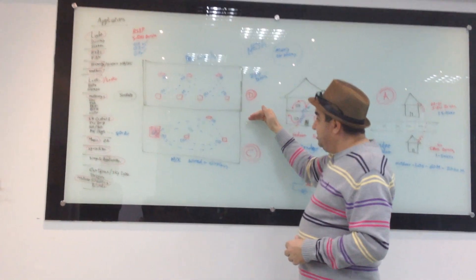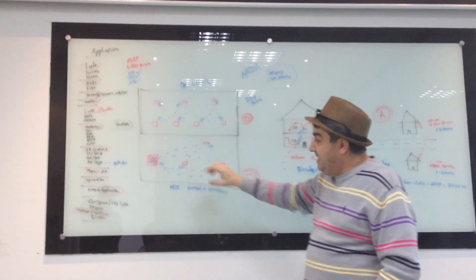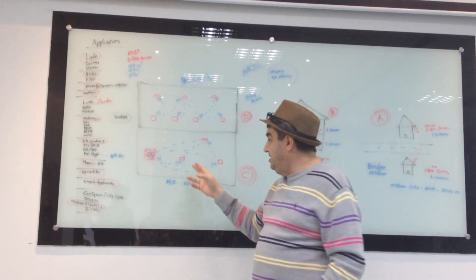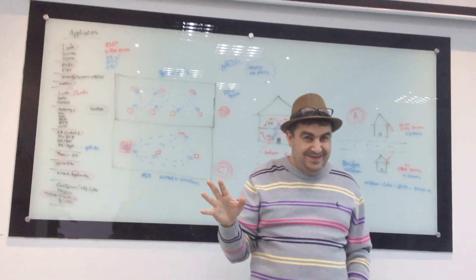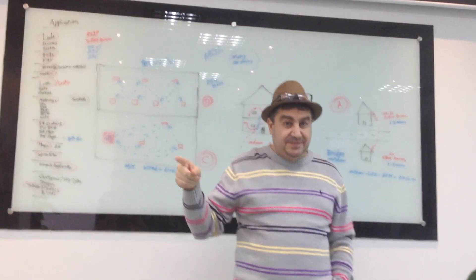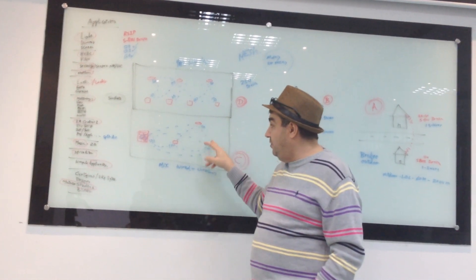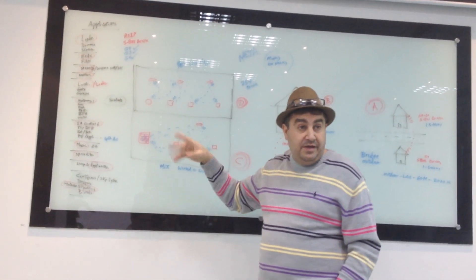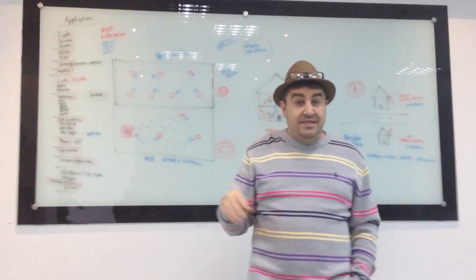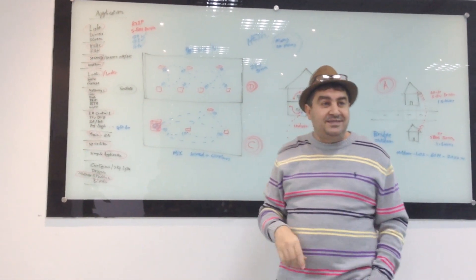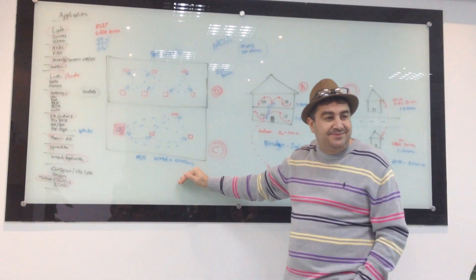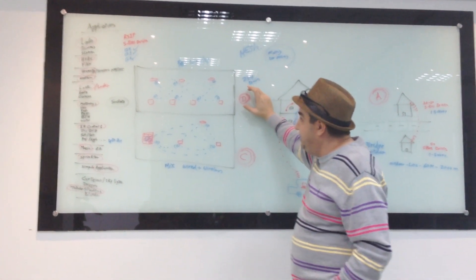We have another solution which is a mix of wire and wireless. Let's say in the DB I can locate all my dimmers, my relays, my HVAC and other things. But I cannot connect my DDBs and switches and motion sensors by wired cables, by bus cables. So in this case only I put Z-Wave behind every DDB or 6 button, 3 button, or IR emitter or motion sensor, etc. And then I have a mix where these can control the wired devices in the DB. So this is a mix between wire and wireless, it's a hybrid system.